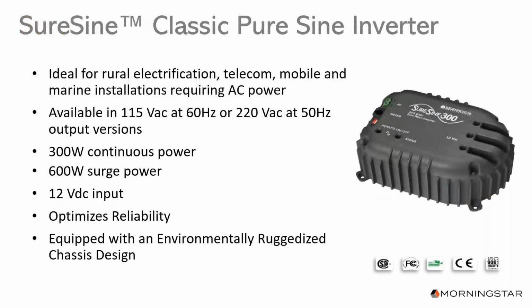Here you can see our classic SureSine off-grid inverter, first introduced in 2006. Just like our new SureSigns, it's ideal for rural electrification, telecom, mobile, and marine installations that require AC power. It has a low self-consumption of 450 milliamps when powering loads. During no-load conditions, the SureSine automatically powers down to standby mode, reducing self-consumption to 10% of operating consumption. It's available at 115 volts 60 hertz or 220 volts 50 hertz, provides 300 watts continuous power and 600 watt surge peak rating for up to 10 minutes. It has a 12 volt input, is highly reliable, and features an environmentally ruggedized chassis design.